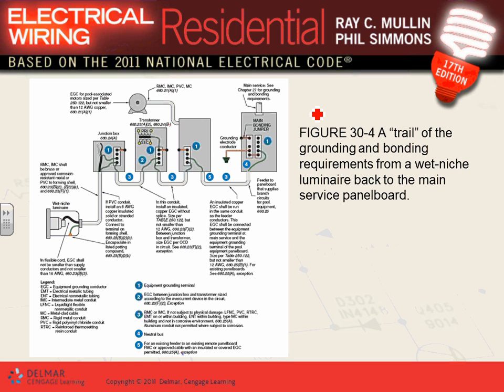The second thing is lights. Here's a light that you put inside the swimming pool. You see the swimming pool light. This happens to be a wet niche light. Look what they do. They bring an equipment grounding conductor. See that green? There's a lot of conductor, number 12 at least, that goes all the way from the panel, bonding them. I don't know if you guys can see the green all the way. Bonding all this equipment with conductors that ground all these objects.